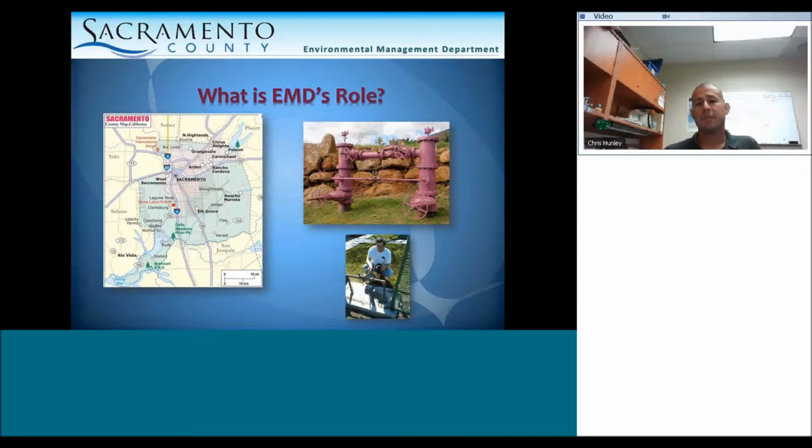What does the Environmental Management Department do to help prevent these types of contamination incidents from happening? Since 1987, we've worked with local water purveyors in protecting their systems from backflow contamination. We're contracted to ensure that facilities and operators install the appropriate level of backflow protection at their facility, that they have those plumbing appurtenances tested every year or more often if needed, and that certified backflow testers are the folks who go out and perform those tests to make sure they meet standard operating conditions and procedures.